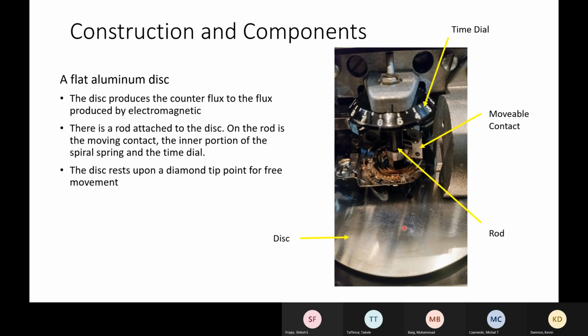So typically this disc is just flat, smooth. It was brought up in the last class, and I can't remember who asked about it, but I have seen this have some bumps in it. I haven't been able to find anybody that knows why some of them were manufactured that way. But this is a lot more common, as it's just a smooth disc, because all you're doing is inducing a voltage on it and then getting circulating current and creating a torque. So this is the central rod that goes through it, and the disc is attached to it. Here's my movable contact.